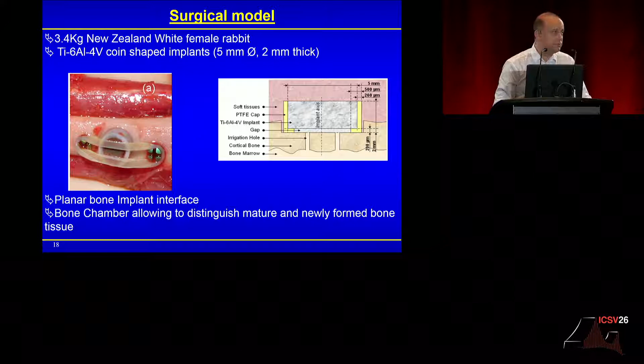So we immersed it in a tank, and then we used a very simple focused transducer, 15 megahertz. And so we made sure that the axis of the transducer is perpendicular to the implant surface. And then we had a displacement of the sample in order to have a scan of the surface. And the transducer was working in a very simple echographic mode, so that you have an echo. And the echo that you get in this kind of system is quite simple. The first echo is the echo of the water implant, okay? Then the wave propagates inside the titanium, and then you have an echo of the implant bone interface, and that's the implant bone interface that we are interested in.